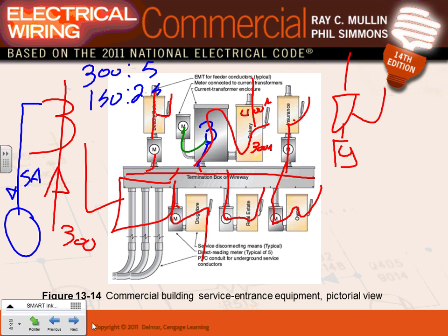They want to change. Then you have to go check, do you have enough juice here? Okay, so this guy is right now 200 amps. He wants to go to 400 amps, right? Even in that case, no problem. We get you an arrangement like this here. We take this out, but before you do that, do we have enough juice here to feed the extra load? That's why they hire you to analyze the system. So they hire an engineer like yourselves, guys, to go do a load study on that.